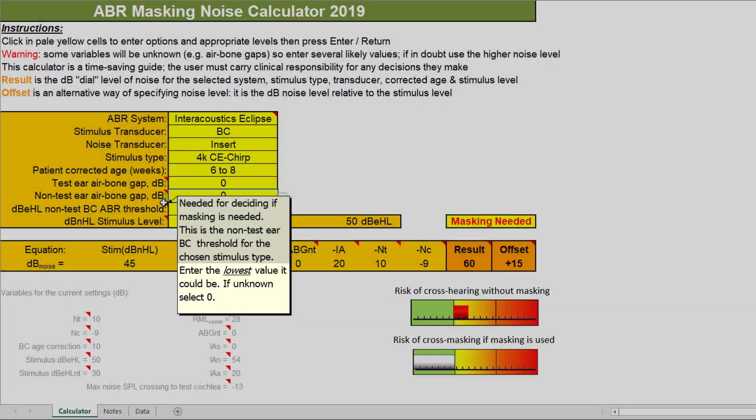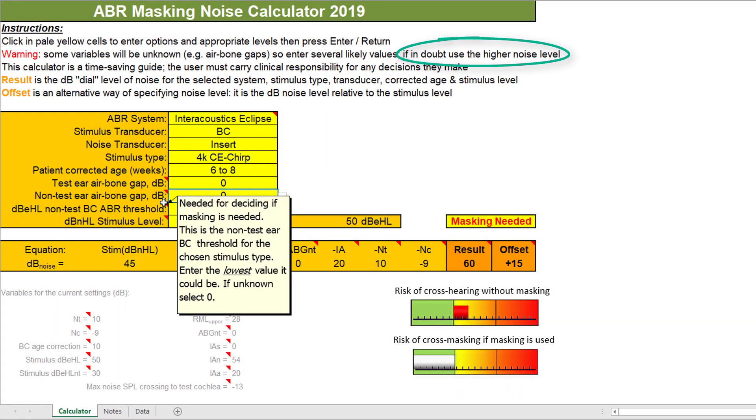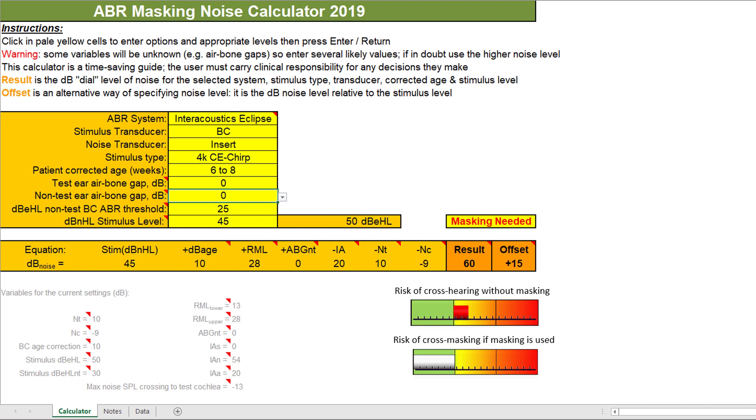This will ensure a greater amount of masking is applied in order that you can be confident that the non-test ear cochlea is being sufficiently masked and is not therefore contributing to the response. Once you have entered your values into the calculator, assess the risk of cross-masking and the likelihood of cross-hearing, the calculator will provide you with two results for each scenario that you explore, a result and an offset. The result is the dB dial level of masking noise that you should apply to your non-test ear and the value that you should enter into the Eclipse software.